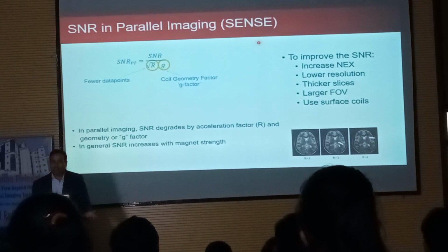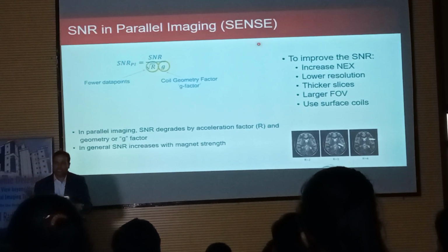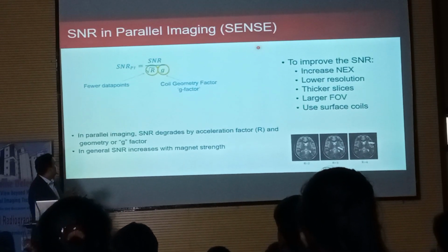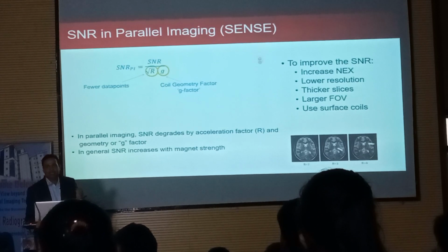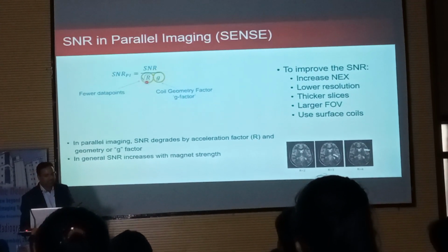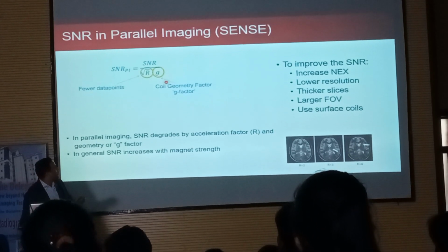Like parallel imaging, everyone knows about it, whenever we do the DWI or DTI, we do the parallel imaging, like SENSE, GRAPPA. So there SNR doesn't stay at the native pure SNR. It gets further reduced by the acceleration factor as well as the coil geometry factor.